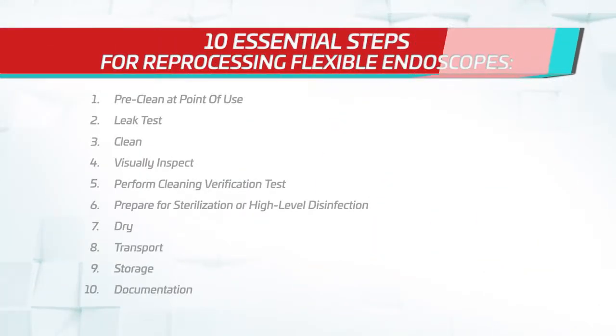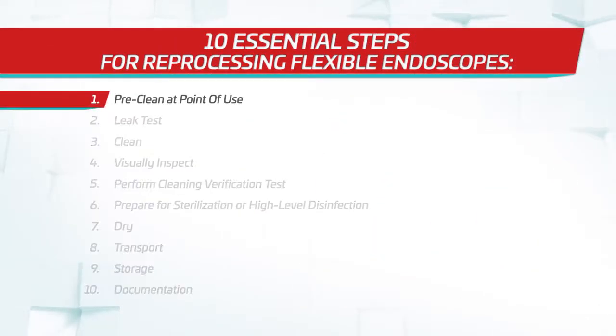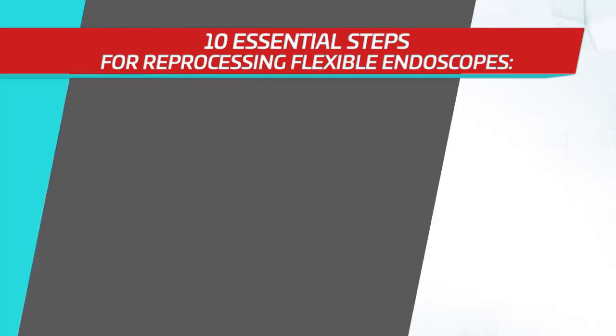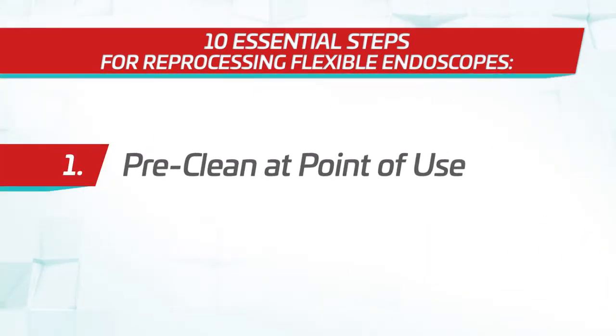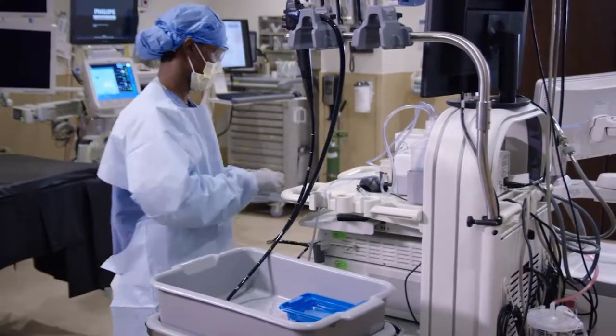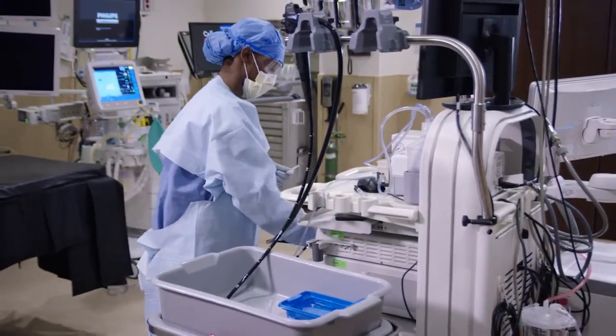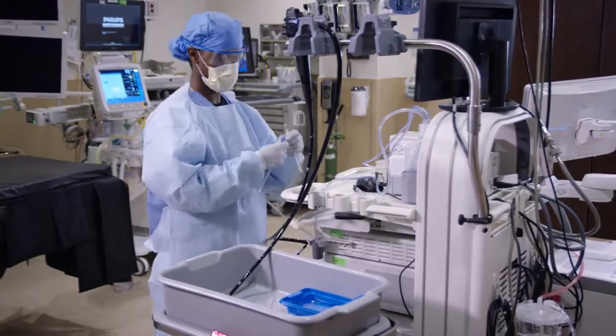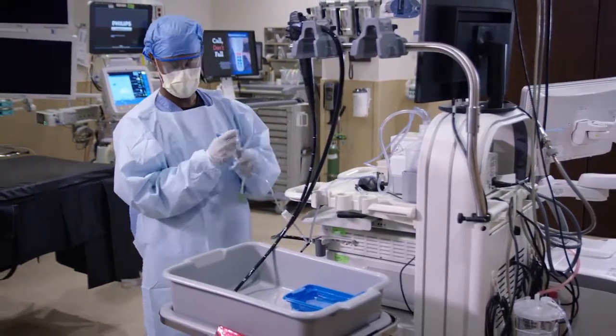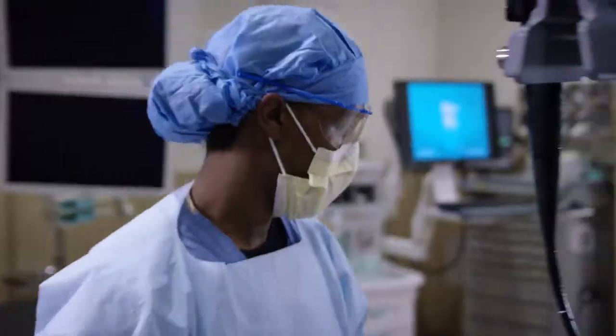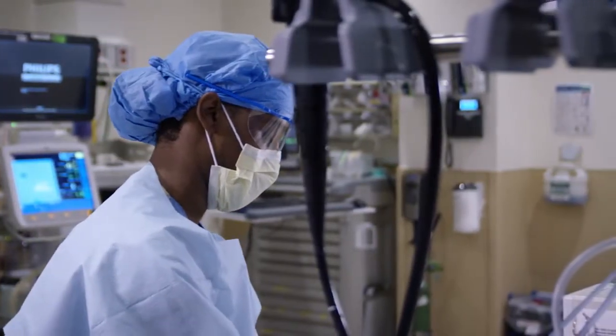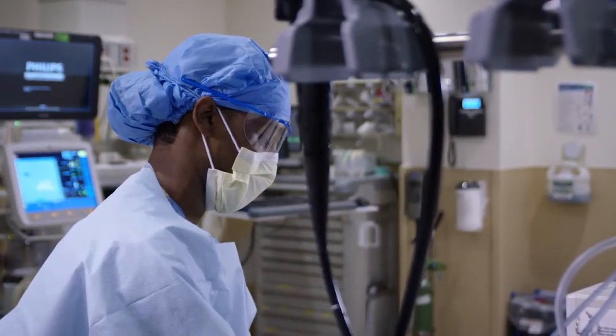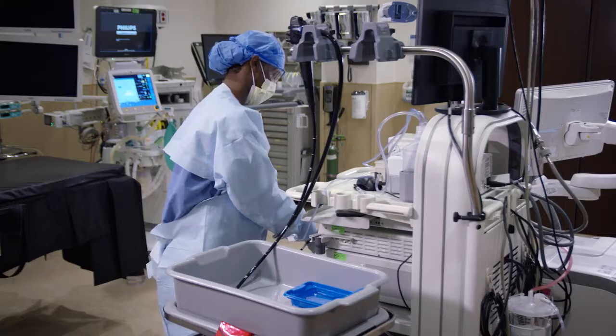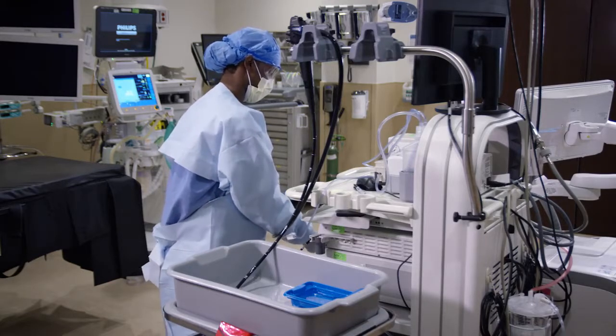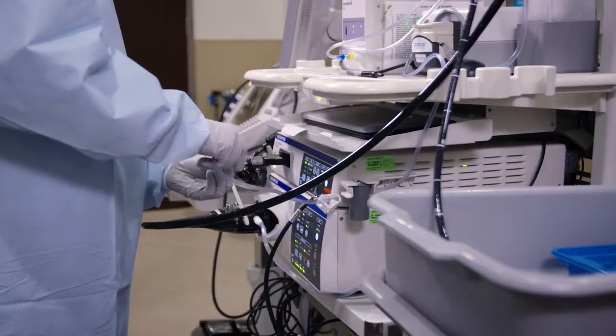Let's begin with the first of our 10 essential steps for reprocessing flexible endoscopes: pre-cleaning at point of use. Pre-cleaning should begin immediately following the completion of the procedure. Blood and soil that dries can facilitate microbial growth and increase the risk of biofilm formation, which can double every 20 to 30 minutes. And once biofilm grows, it is difficult or impossible to remove.